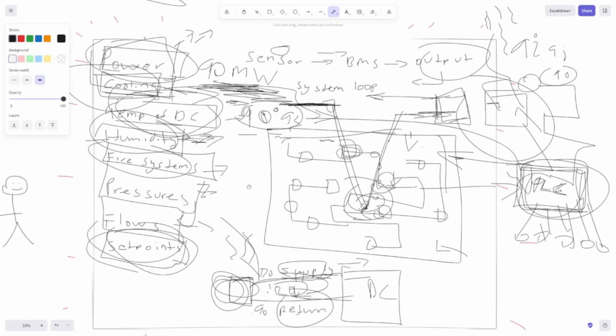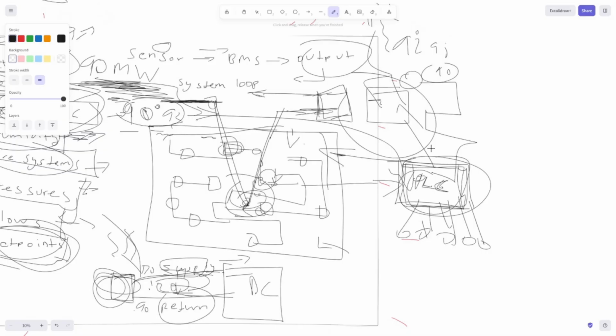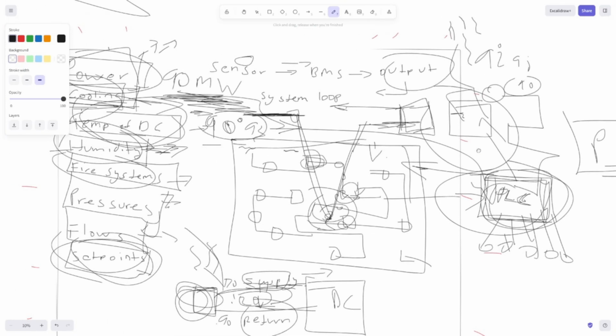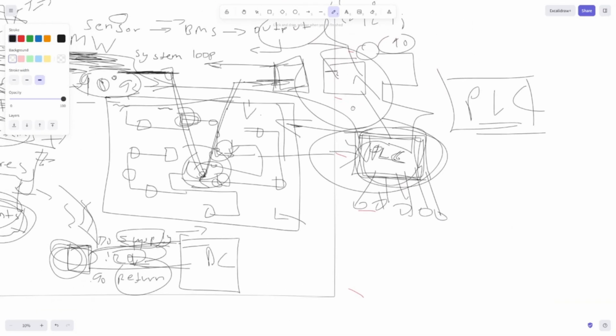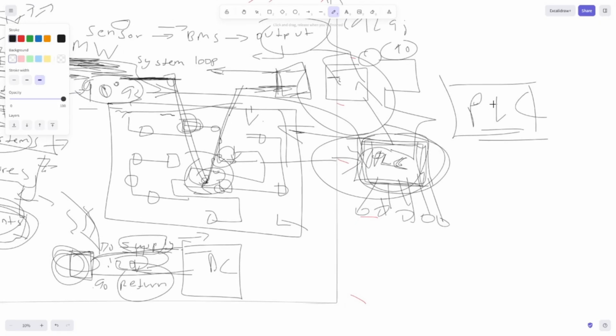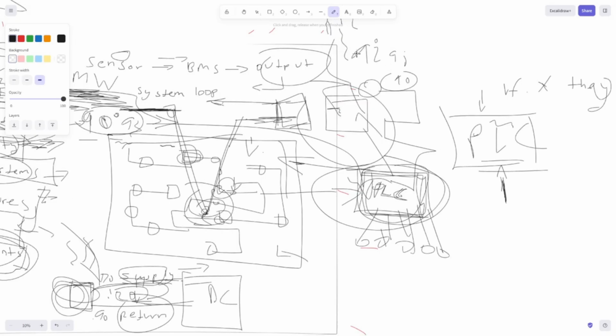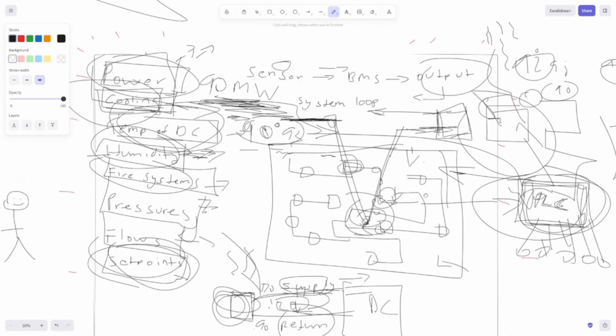If you go really deep into it, the most difficult part gets to when you start talking about PLCs. From here, you're not talking about a building engineer anymore. You're talking about a controls engineer now, because a PLC is a programmable logic controller. I'll talk about this later as well, and this is kind of the field that I'm wanting to get into. What it does is it has logic embedded inside of it that tells it, if X has happened or has not happened, then Y happens. If I'm at 92 degrees and my set point is 90 degrees, then I'm going to turn on the chillers until I'm at 90 degrees, then I'm going to turn off the chillers. That's basically what a PLC is.